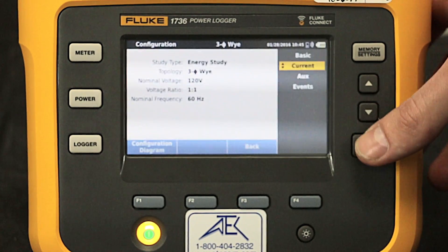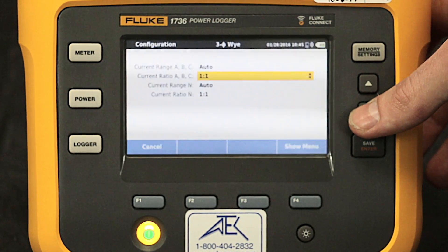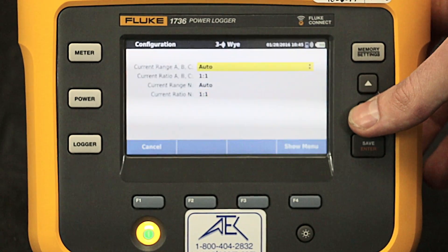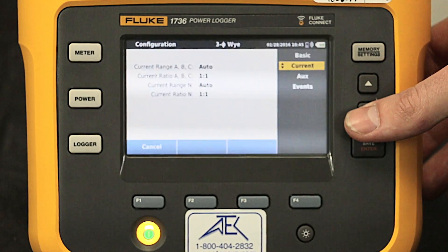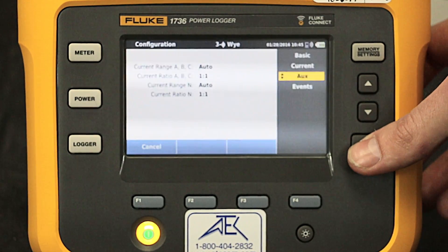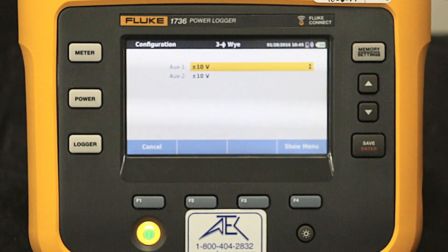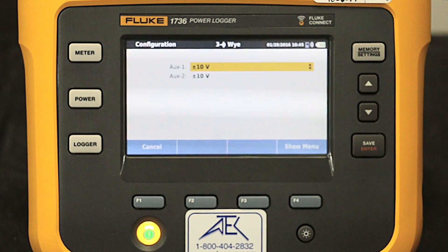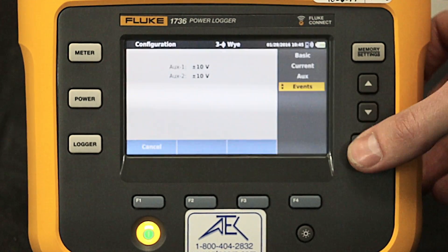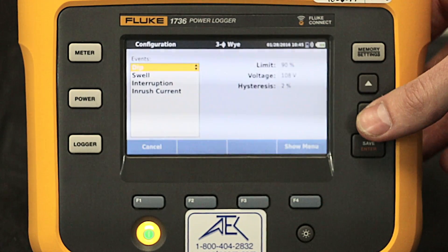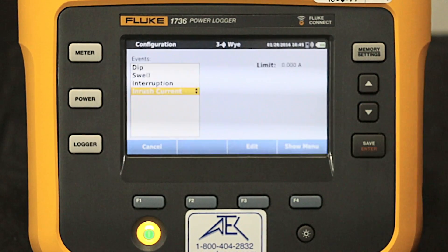Additional menus are available by clicking the Show Menu. Dropping down to current, we can see the current range is set to auto, which is the preferred setting. Other configurations available are auxiliary, which is for sensors such as thermocouples, and events such as dips, swells, interruption, and inrush current.